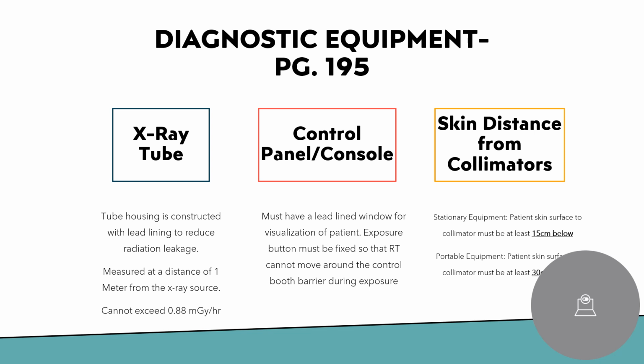So starting on page 195, with the X-ray tube, the tube housing is constructed with lead lining to reduce radiation leakage. The measurement at a distance of 1 meter from the X-ray source cannot exceed 0.88 milligrays per hour. For the control panel, which is on page 196, it must have a lead-lined window for visualization of your patient. The exposure button must be fixed so that the RT cannot move around the control booth barrier during exposure.